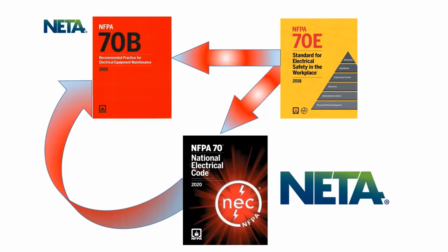No. If I'm going to do diagnostic testing and I've got to touch it with meters, I've got to have it on. If I'm doing any kind of infrared, you've got to have the gear on, warmed up and under load. So there are certain conditions where it has to be on.